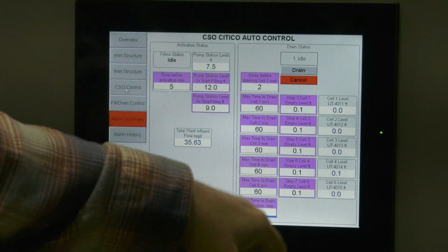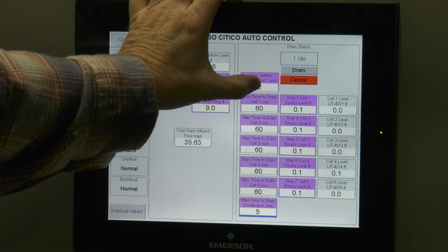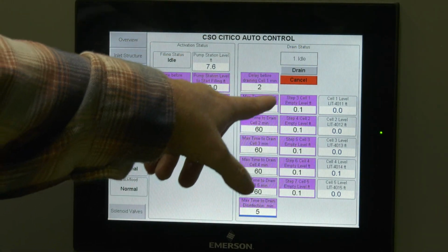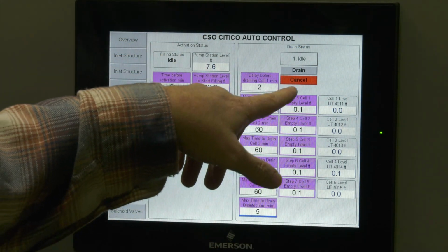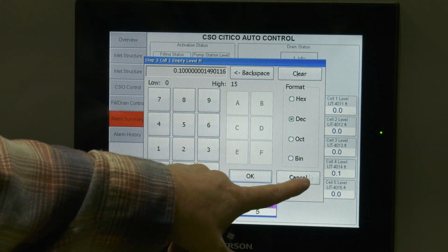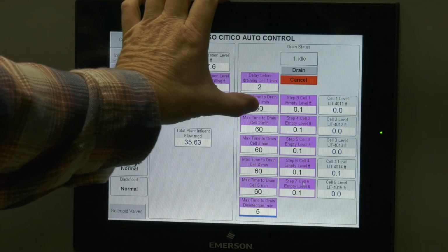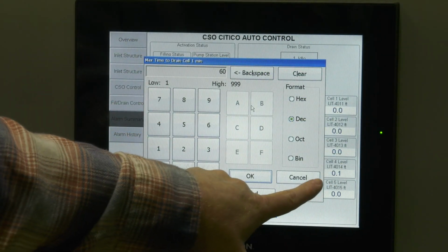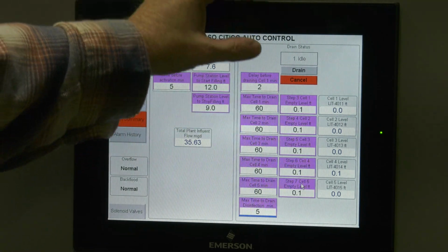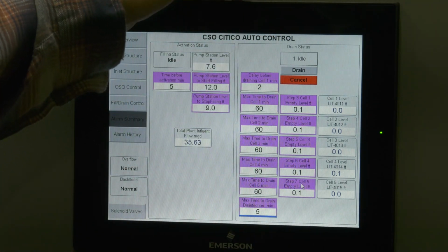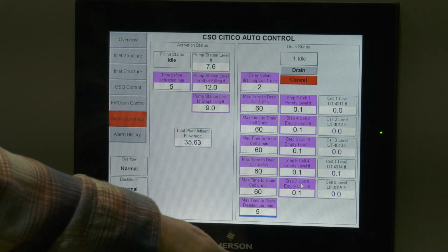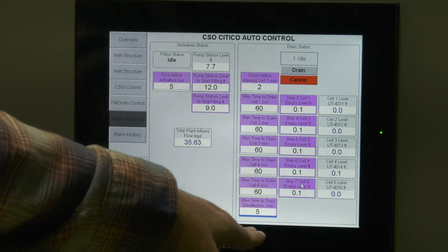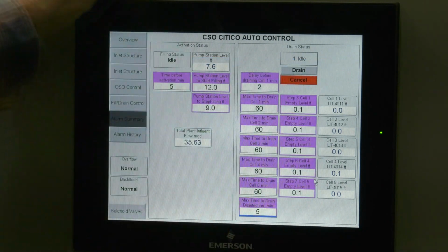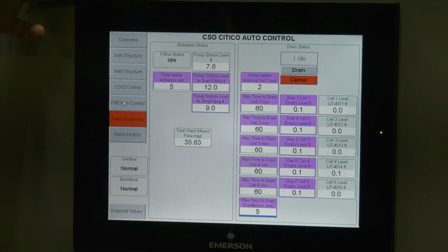And to go into the drain sequence, you hit the drain valve to initiate the sequence, and then for each cell, after a 2 minute operator adjustable delay draining time, it looks at the level of each cell, and if it's less than 0.1, operator adjustable, or the 60 minute set point, which is also operator adjustable, it'll move to the next cell and open the gate and drain it. So then it gives you a max time set to 5 minutes for drain disinfection, again operator adjustable. And let's see, anything else on here we really need to discuss?